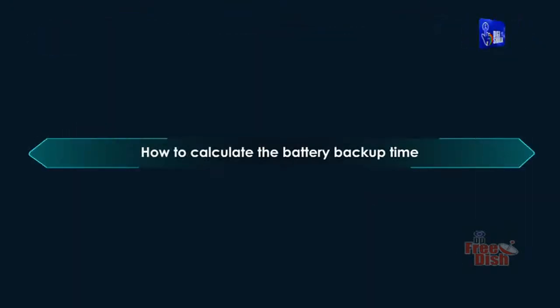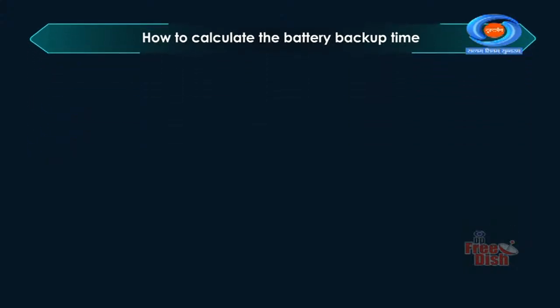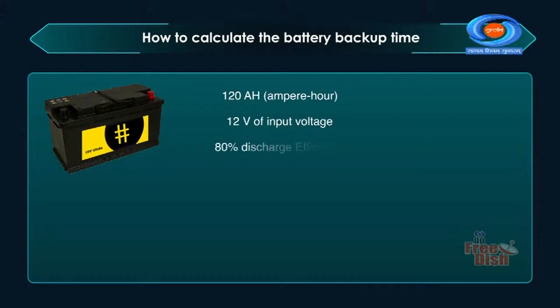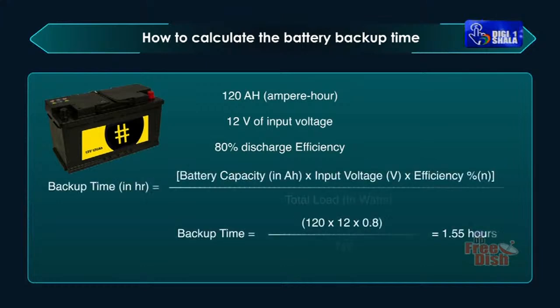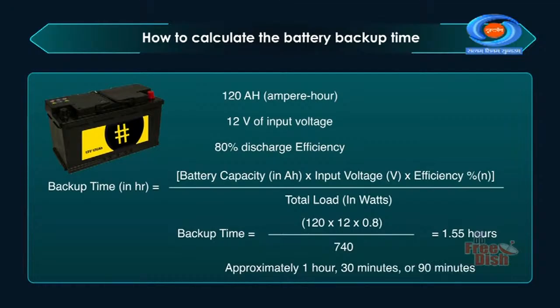Let us discuss how to calculate the battery backup time. Let's assume you have an inverter battery with 120 ampere hour capacity, 12 volts of input voltage and 80% discharge efficiency. Substitute the values in the formula. Backup time is equal to 120 into 12 into 0.8 by 740 is equal to 1.55 hours.